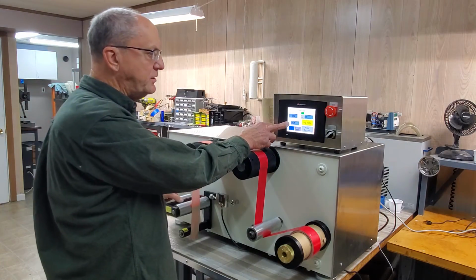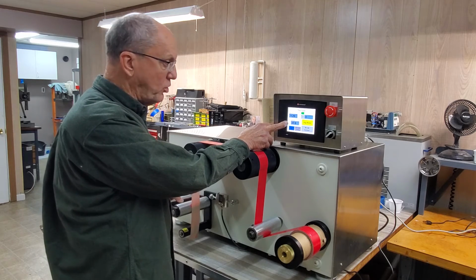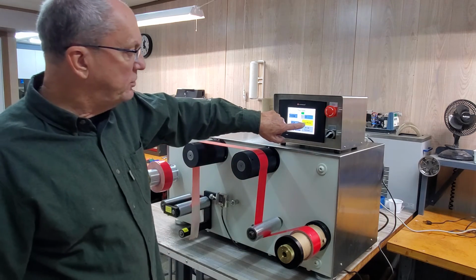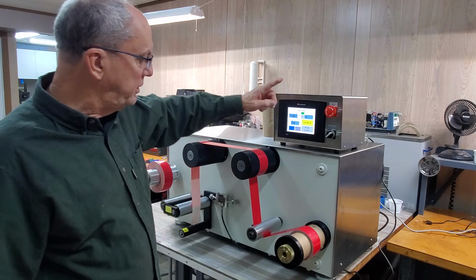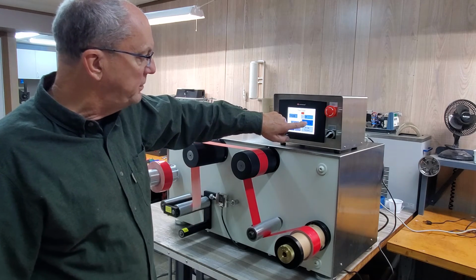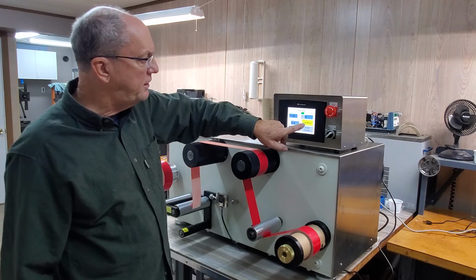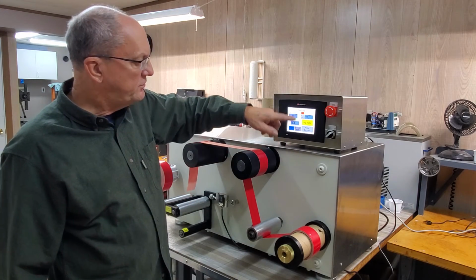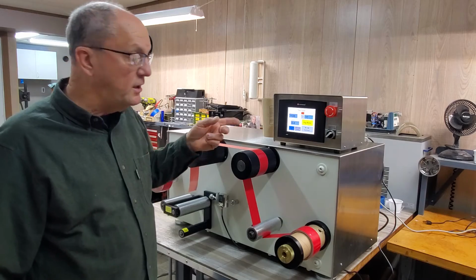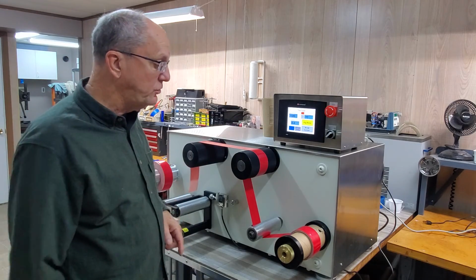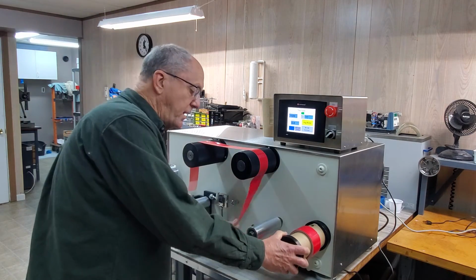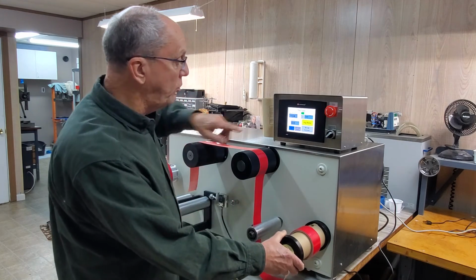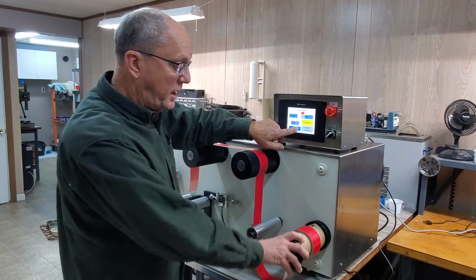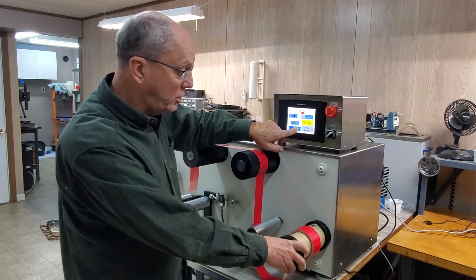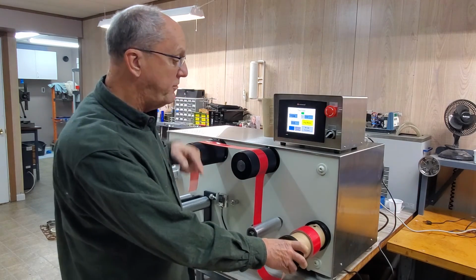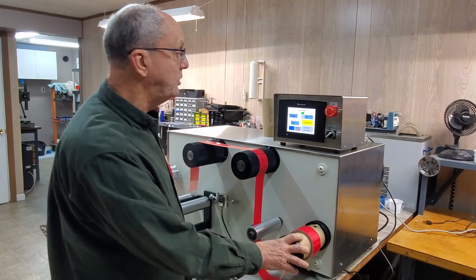Here's our calibrated tension, which essentially is our calibrated number. We have this button here. We can just jog the motor slowly to make sure that the motor is working properly. If you come up here, you'll see this indicator that's flashing red to green. That's the encoder inside, so that says that it's measuring the length properly and so forth. Right now, I have no tension on the clutch whatsoever, but if I hold this button, now I have pretty substantial torque on this clutch. So this is a way for us to test to make sure that the clutch is working properly.